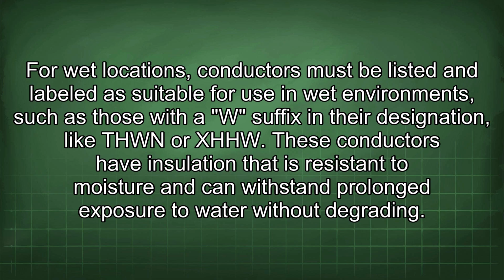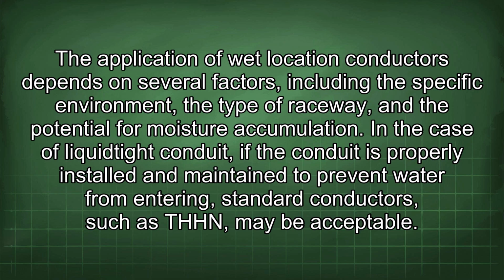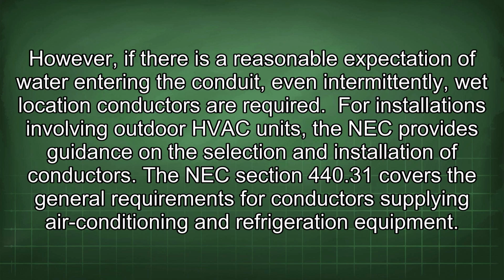These conductors have insulation that is resistant to moisture and can withstand prolonged exposure to water without degrading. The application of wet location conductors depends on several factors, including the specific environment, the type of raceway, and the potential for moisture accumulation. In the case of Liquidtight conduit, if the conduit is properly installed and maintained to prevent water from entering, standard conductors, such as THHN, may be acceptable. However, if there is a reasonable expectation of water entering the conduit, even intermittently, wet location conductors are required.